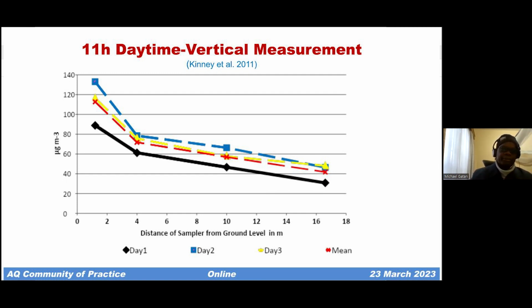In fact, when we calibrate low-cost monitors, we are only reducing the uncertainty. And the scientific basis is optical. In reality, if you look at it in general, the science dictates that for the very small particles, you can get near accuracy. But when you come to PM 2.5, we are only reducing the uncertainty.